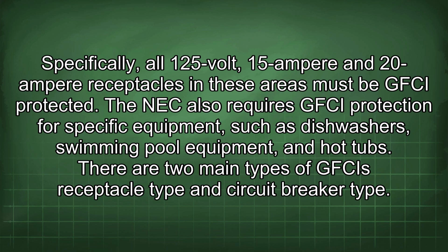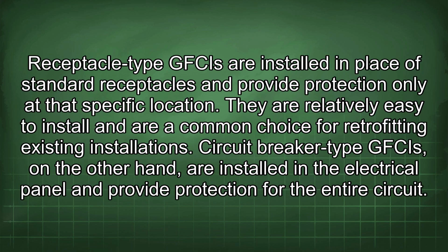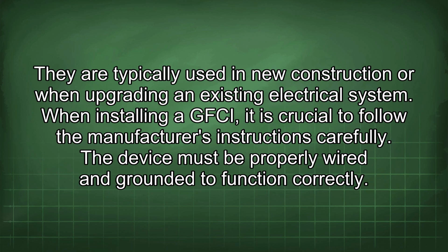There are two main types of GFCIs: receptacle type and circuit breaker type. Receptacle type GFCIs are installed in place of standard receptacles and provide protection only at that specific location. They are relatively easy to install and are a common choice for retrofitting existing installations. Circuit breaker type GFCIs, on the other hand, are installed in the electrical panel and provide protection for the entire circuit. They are typically used in new construction or when upgrading an existing electrical system.